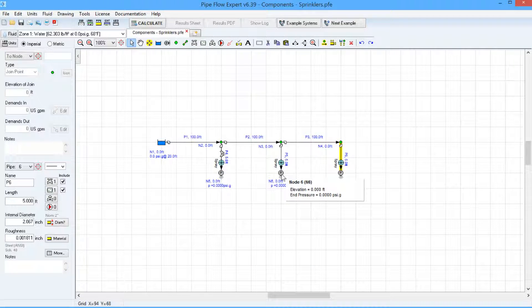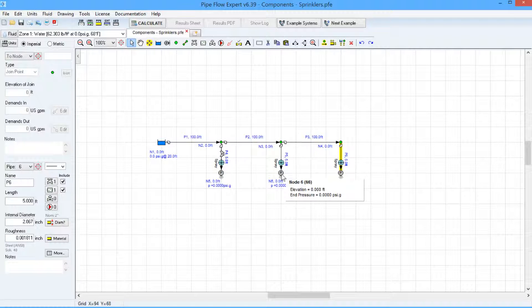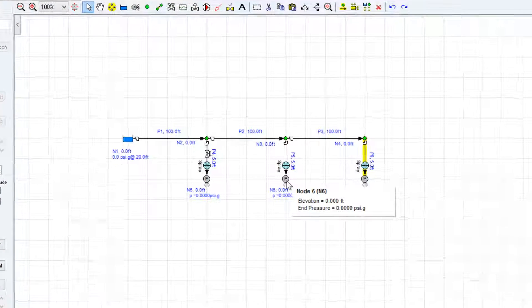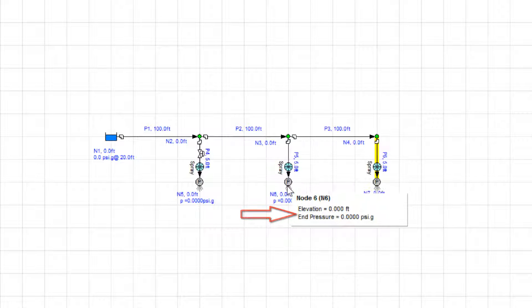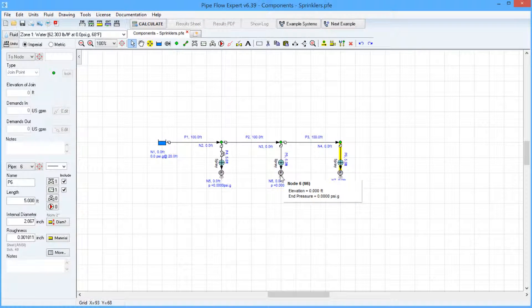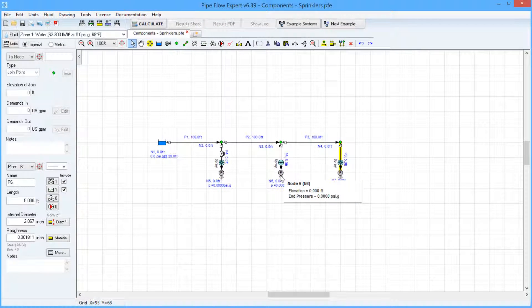Because these nodes are discharging to atmosphere their end pressure is set to zero psi gauge. If these nodes discharge into a pressurized tank then the end pressure would be set to the tank pressure.